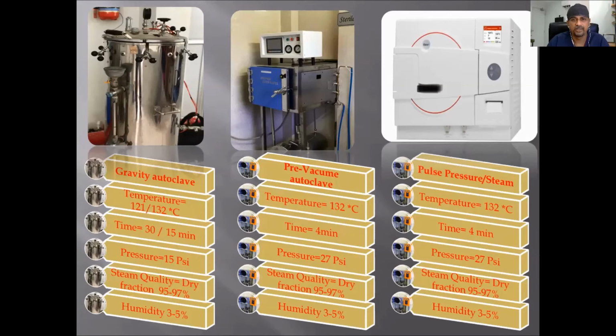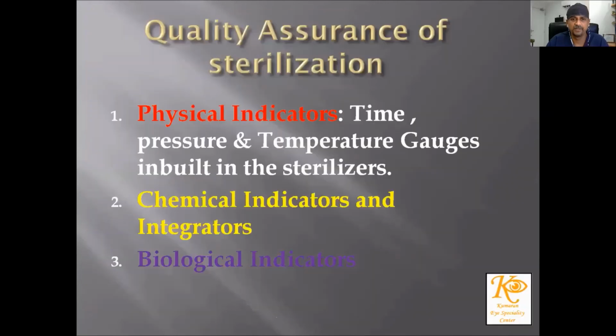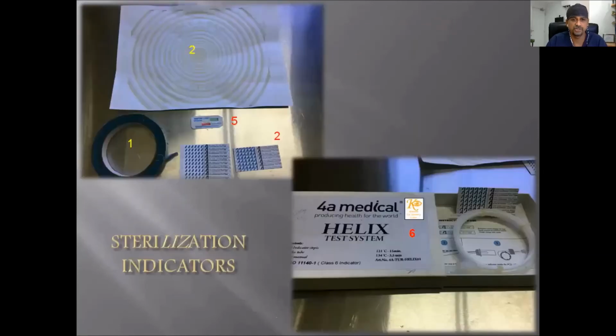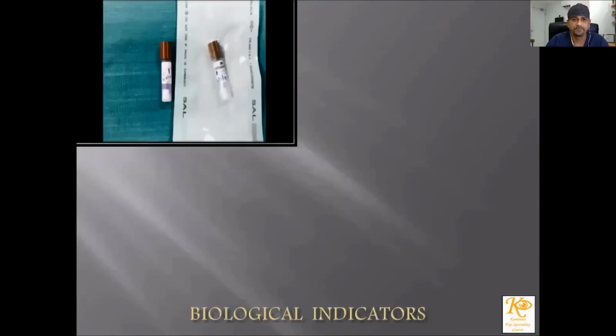In the pre-vacuum autoclave, there's active air removal, where a vacuum pump is on before the sterilization and after the sterilization. This happens just once. However, in the class B or pulse pressure steam autoclave, there are multiple cycles of pressure and steam to remove the air, and it is more effective. The pre-vacuum and the pulse pressure steam autoclaves are ideal for ophthalmic use. Once the sterilization is done, quality assurance is done using physical indicators, chemical indicators, and biological indicators. The different kinds of indicators start from class 1 to class 6.